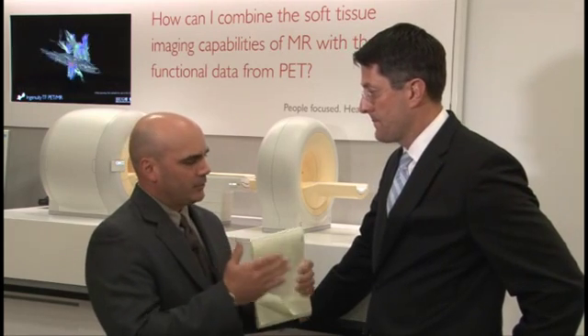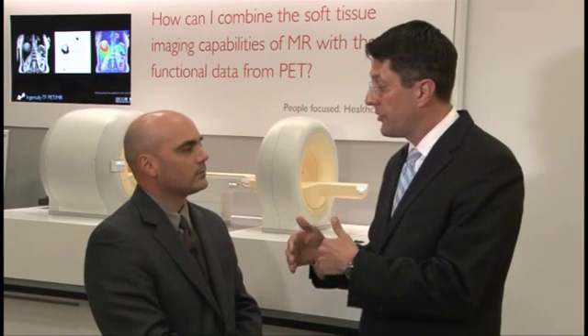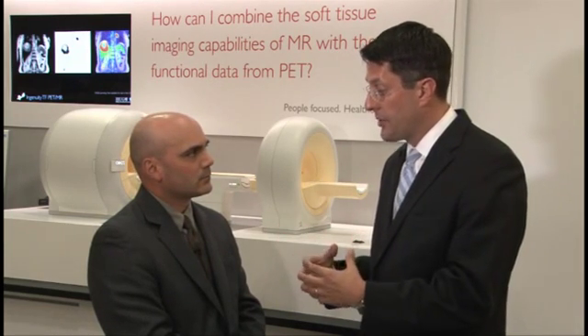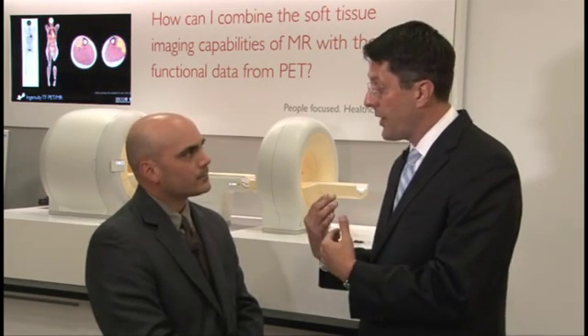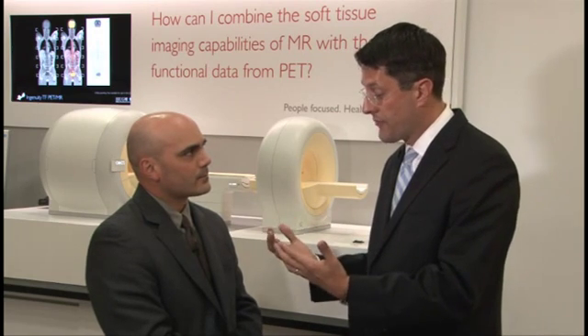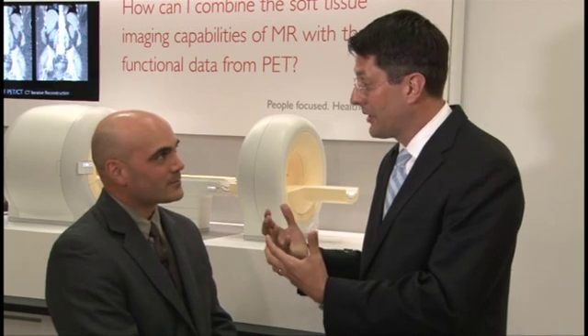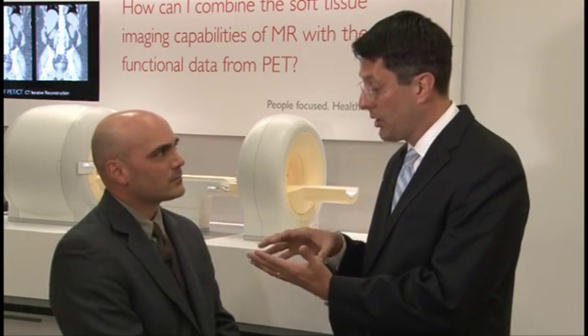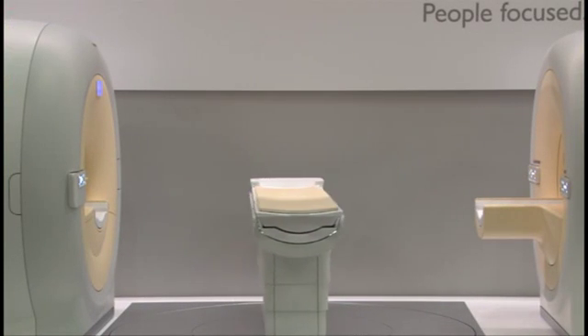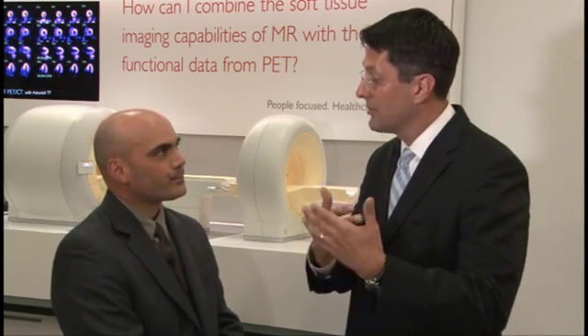Explain how your system works — you have your MR and your PET system in the same room. Exactly. Just like PET CT today, it's really a sequential exam. We've got two systems with one patient table that drives registration between both systems. The patient will have the MR exam first for registration and attenuation correction, then move for the diagnostic PET workup, and then if needed come back to the MR for additional diagnostic work. The flexibility of the system is really the driver, but also the performance of time of flight on the PET and the premium 3T applications on the MR are the key drivers. Maintaining that registration with the same algorithm we use with PET CT, but using that technology for PET MR, really drives accurate fusion between the two devices versus relying on software correction.